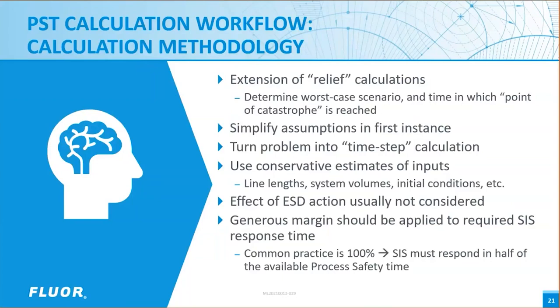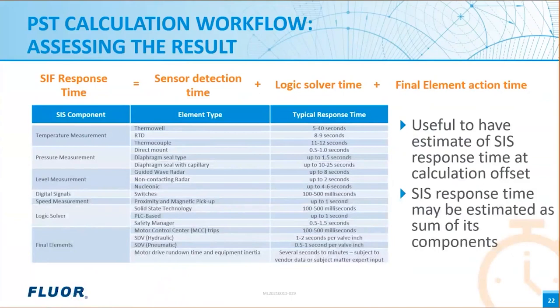Or conversely, we require that the safety instrumented system responds in half of the available process safety time. And sometimes that can be really difficult to achieve. So I think it's useful if process engineers and the people doing these calculations have some way of estimating whether a process safety time calculation gives them a sensible answer or not. So we can do that by estimating what our safety instrumented system response time is.